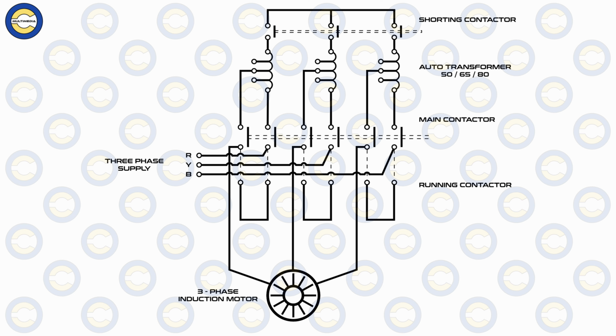Now, let us understand a typical flow that happens. When the motor is to be started, the main switch and the main contactor close, supplying power to the circuit. The running contactor during this particular time remains open initially. However, the shorting contactor closes, connecting the motor to the auto transformer. At this stage, the motor receives a reduced voltage depending on the transformer tap selected, and hence it draws a much smaller current from the supply.